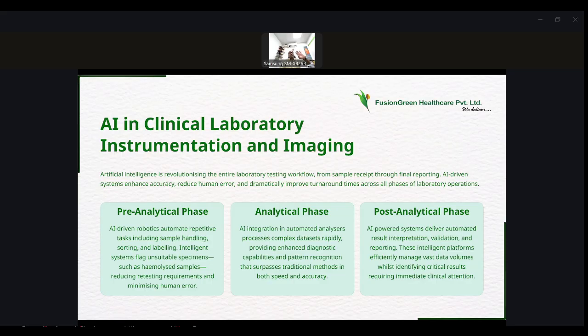Suppose the indices are high for the patient sample, then the serum indices mode will automatically be on in the analytical phase. For the excess interference, depending upon the parameter, the concentration will be adjusted either by sample or by the reagents in the spectrophotometer. In turn, it will give you the exact results. So the analytical phase is an automated analyzer processing complex data sets rapidly, providing enhanced diagnostic capabilities and pattern recognition that surpasses traditional methods in both speed and accuracy. When the pre-analytical is 100% correct, the analytical phase will not have any problem at all.